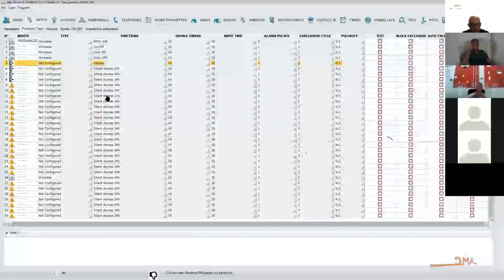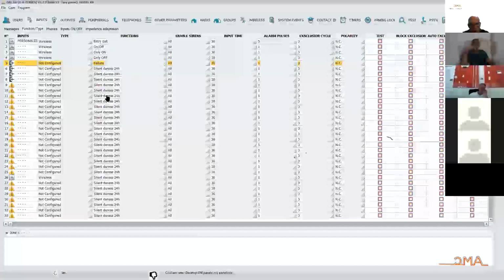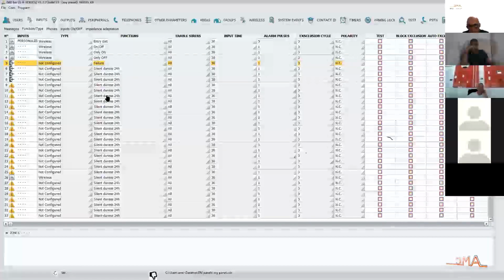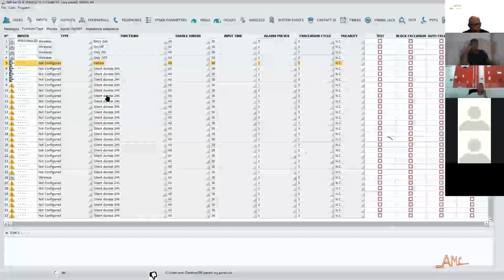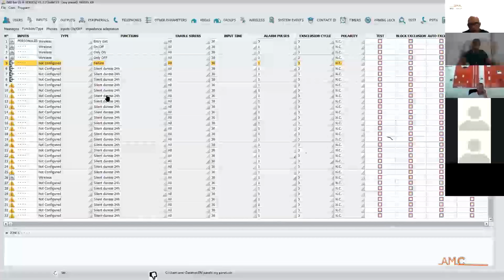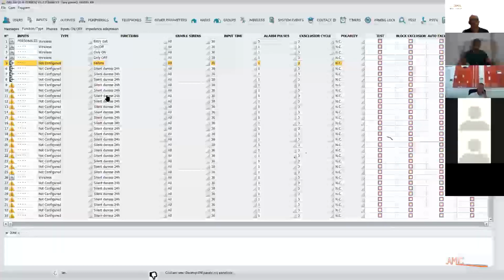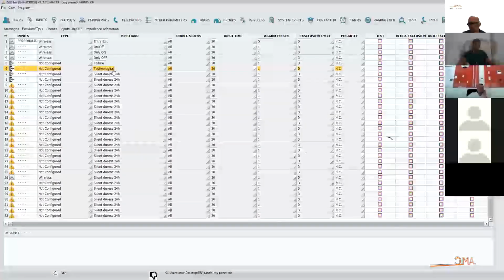I mean, if you decide to connect an external security device to our panel, for example, a smoke machine or other, it is possible to connect this zone to the external machine to have a trouble report of the external machine. This zone is mandatory for EN approval, okay? Because it's possible to use, for example, the failure zone, but it's also possible to use the technical zone, for example. It's possible to use the same zone, okay?